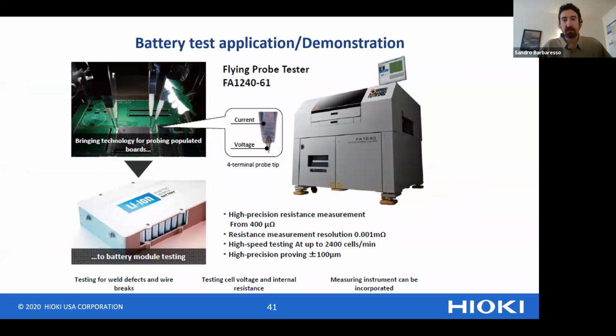So the concept of the 1240-61 is similar to the test of a PC board, with almost the same speed. It offers very low resistance measurement, so we can check the welding of the interconnection between the cells. We can go up to a resolution of 1 micro ohm, and that speeds up testing to 2400 cells a minute, with high precision probing up to 100 micrometers. You see the machine on the top right. This is authentic. Next slide, please.